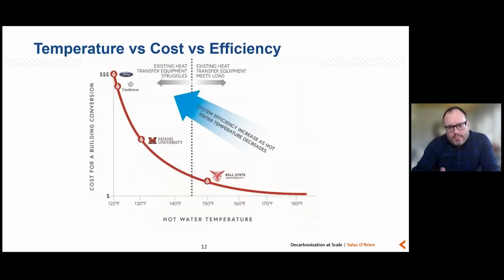I wanted to just briefly touch on the temperature versus cost versus efficiency strategy here. It's very important to select the hot water supply temperature, not only for the technology selection on the heat pump side, but also perhaps more importantly on the cost of the building conversion. So I put in here 4 different projects that we've been associated with recently. Ball State, I said, was designed at 150. It's operating in the 140 range now. Miami is a 130 project.